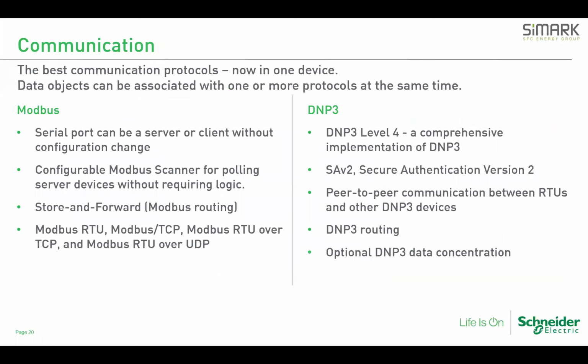Communications: the SCADAPacks are supporting both protocols equally well, Modbus and DNP3. We've added a Modbus scanner into the X70 RTUs. So instead of using our old Modbus TCP communication or Modbus RTU communication function box in code, the user can just use a mouse and a point-and-click environment to configure the scanning and polling, reading and writing of information to devices on the Modbus serial or Ethernet links, as it says here, without creating logic.